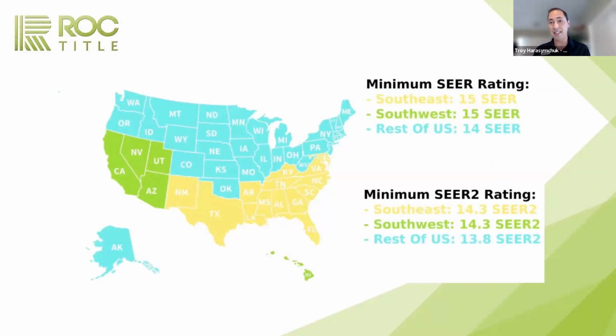Unfortunately, these companies said, "Yeah, these are 14 SEER systems. We're basically meeting the standards." Then they put it into a controlled environment. And they realized, no, they're like 12.8, 13.1. So they actually changed and put a more stringent standard on there, and that's why the prices went up. So really, it's the end consumer that actually has to pay the price. So if you notice here, it's 15 SEER. Or technically with the new SEER standards, our 15 SEER is 14.3. So we really didn't seem to go up, but these are a little bit more accurate ratings.